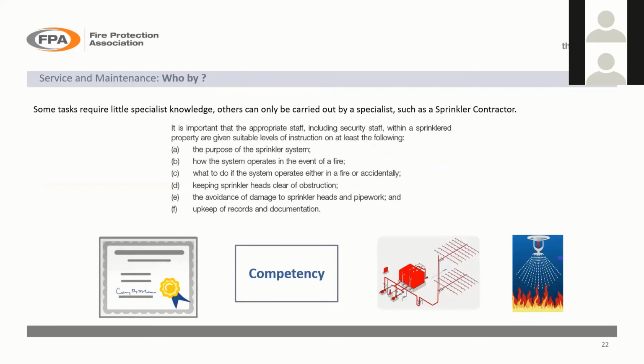So some tasks, when we're looking at who carries this out, require little specialist knowledge, while others can only be carried out by a specialist, such as a sprinkler contractor. It's important that the appropriate staff include any security staff, because in a lot of buildings, obviously, they operate from 9 to 5, so there's security staff on site in the evenings. I'm thinking perhaps office blocks and that kind of premises, or shops or shopping centres. They might be the only people on site, so if anything happens at all, they should have some awareness of the sprinkler system, and they should know what to do in the case of an emergency. They should really know the purpose of the system and how it operates in the event of a fire.